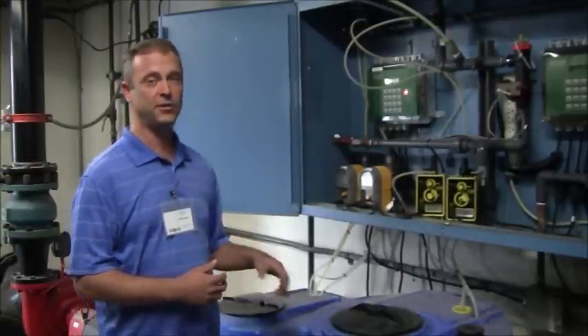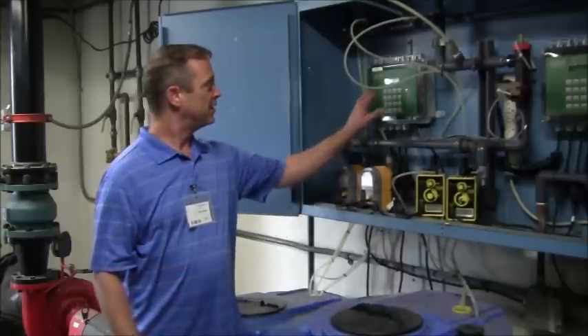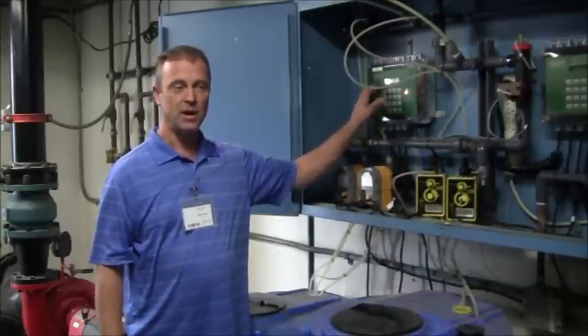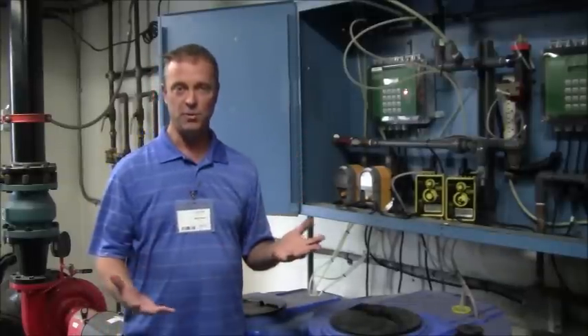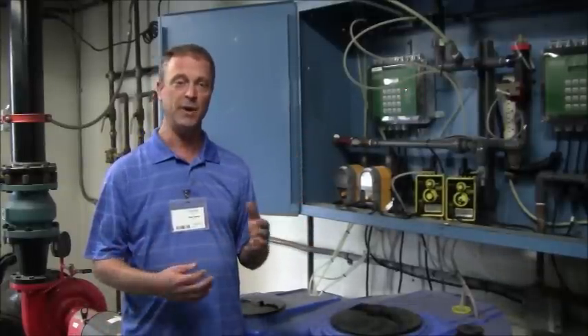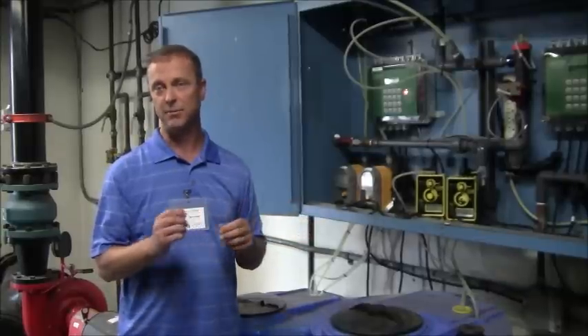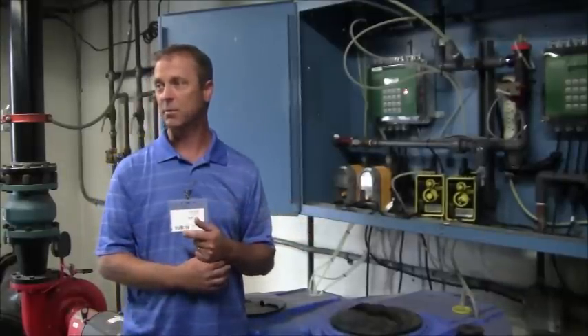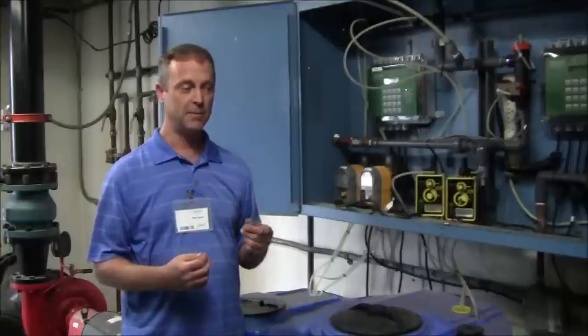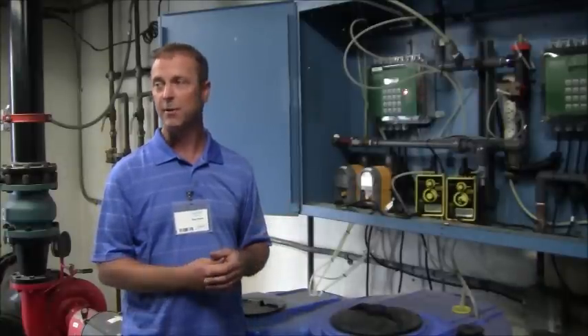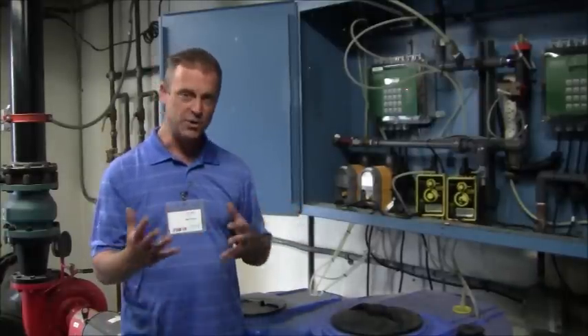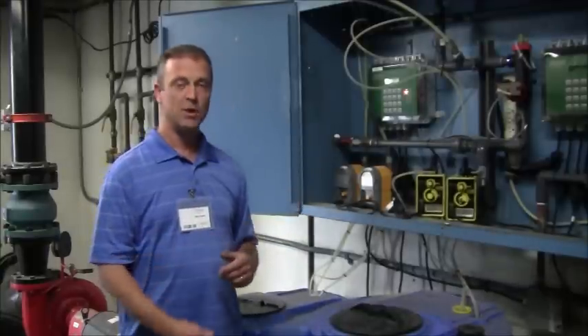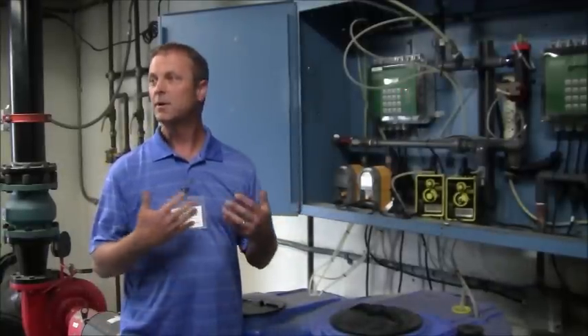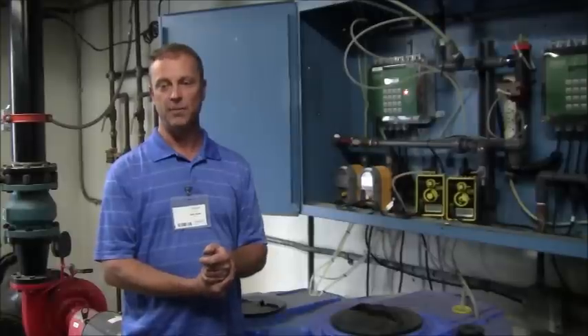So bromine is the product that we're feeding. The controller has a feed schedule timer throughout the week. It's up to your water treatment professional to program that, and we can test it using dip slides and monitoring to see if we're taking care of the microbiological growth in the tower. And so you can just increase your programming and feed your bromine or your oxidizer according to the results you get from your testing.